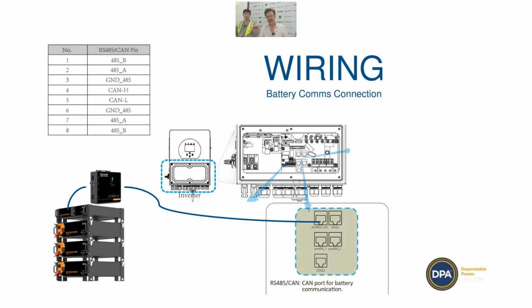Not all of the Deye models have this configuration. Some of them just have a CAN bus RJ45 plug, and it only has CAN bus on it and doesn't use the rest of the pins for anything else. And so you can just use an off-the-shelf cable. But some of the time, some of the models have this setup. So I'd recommend you just run the CAN high and low, so pins 4 and 5, and skip the other ones. And check the manual to see if it applies for whichever inverter you're using. But that's a really easy gotcha, that you've wired everything up and you think everything's right, and then it doesn't work because of this.